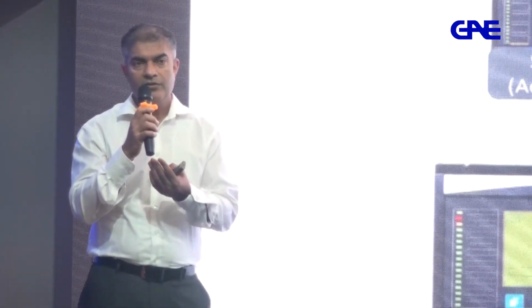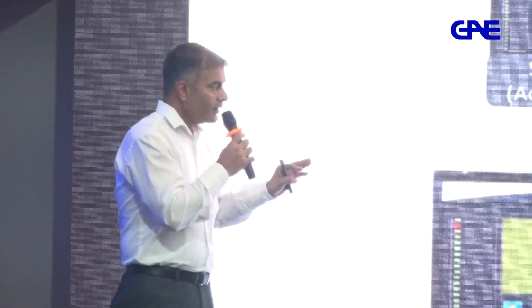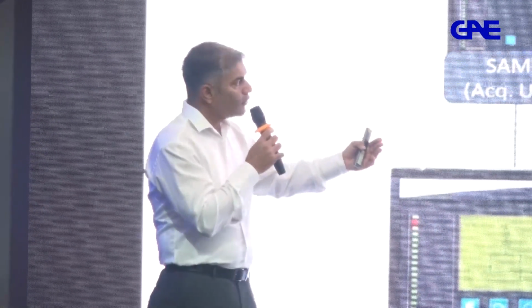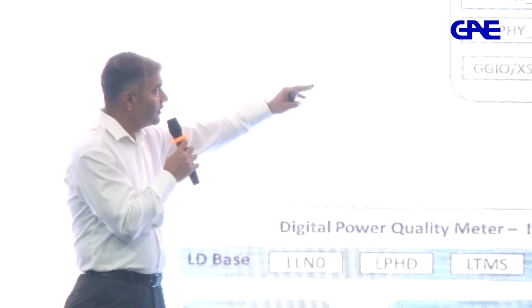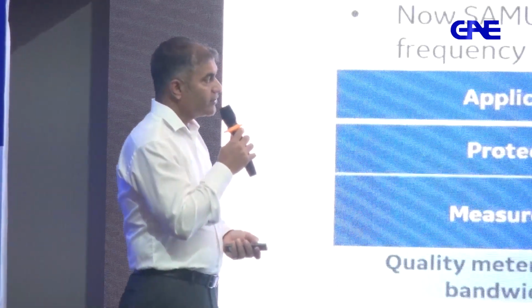This cannot be done with the sampling rate that merging units are doing, but with higher sampling rate like 14 kilohertz, you can monitor power quality. So this is possible, right? Because logically the power quality meter can be driven by sample analog merging unit. So these logical nodes can be put in the field device, and all these logical nodes, they are available. So whatever power quality applications require, those logical nodes are modeled in 61850. It can be possible, right? So this is one more possibility that you can do in digital substation.